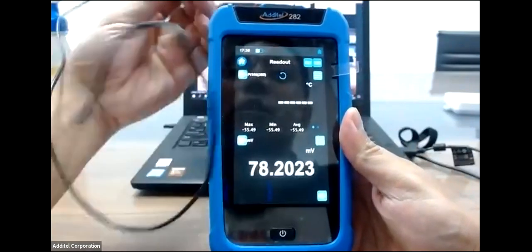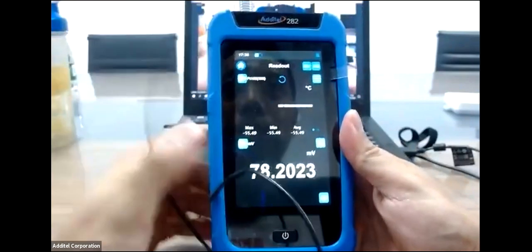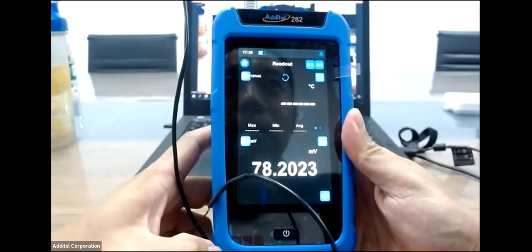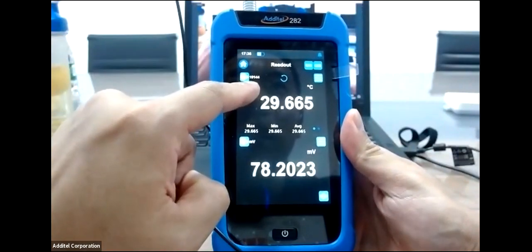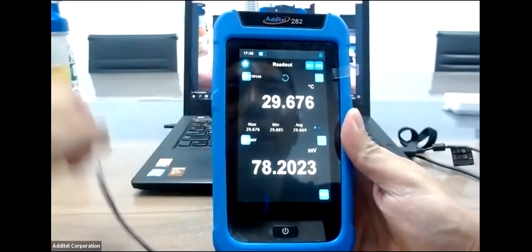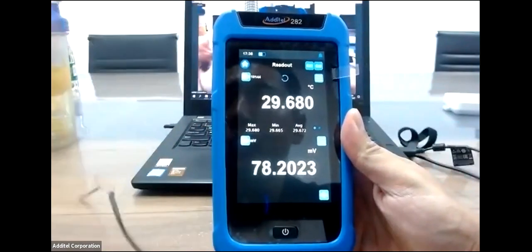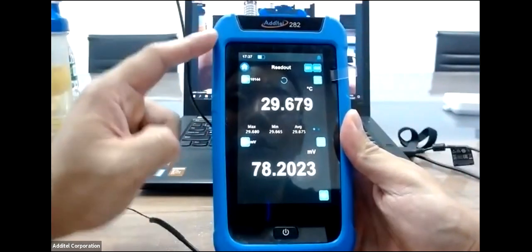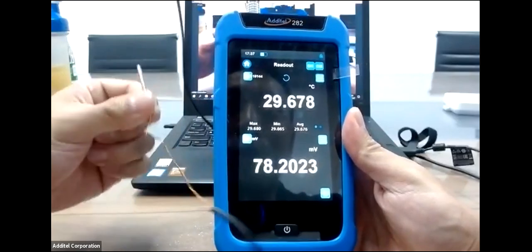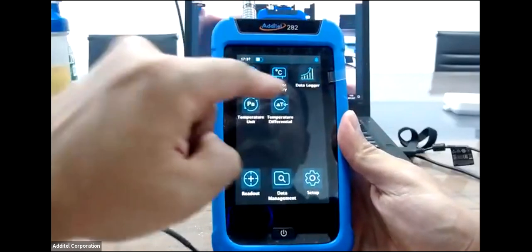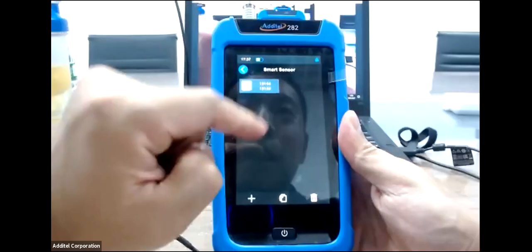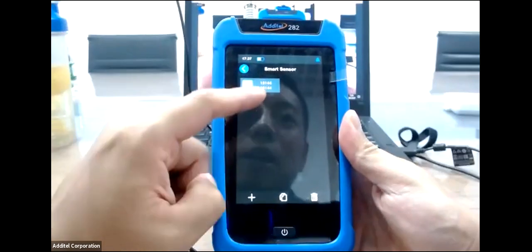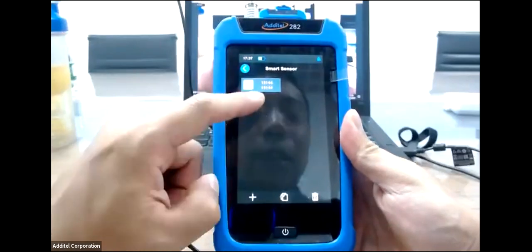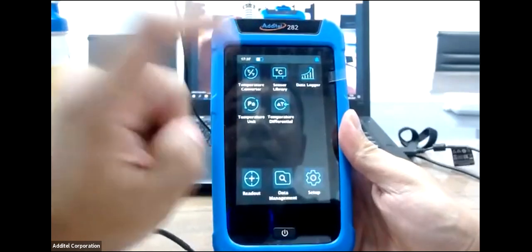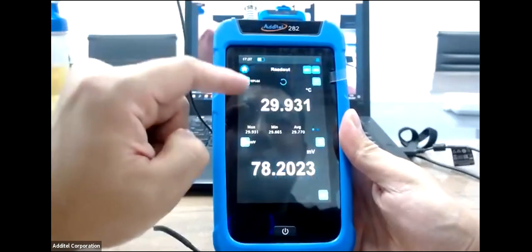Okay, so when I plug in, it will change to 19144, which is the serial number of this probe. So this means this 282 already recognized this probe. So if we check the sensor library, we find that there's one sensor added automatically. This is the smart connector probe.